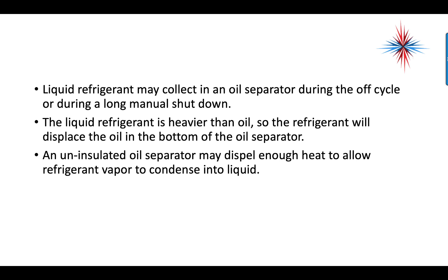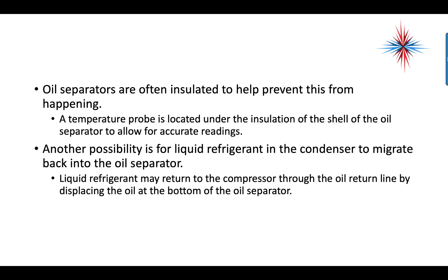Liquid refrigerant can sometimes collect in an oil separator during the off cycle or during long manual shutdown periods. The liquid refrigerant is heavier than oil, so the refrigerant will displace the oil in the bottom of the oil separator. An uninsulated oil separator may dispel enough heat to allow refrigerant vapor to condense into liquid — this is especially important in cold climates. Oil separators are often insulated to help prevent this from happening.